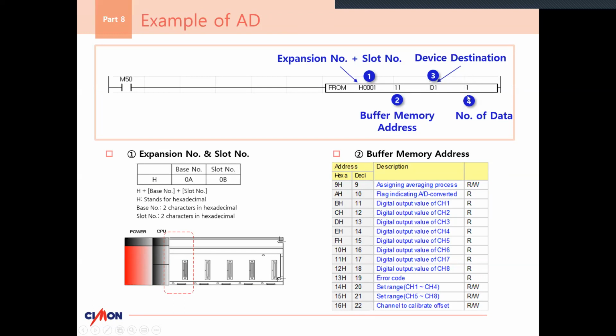If we had a 2 right here, we would want to make sure that we don't touch D2 with anything else, because it's going to send 1 word to D1, and then it's going to send another word to D2 consecutively, depending on what number we put here for number 4. So just to recap, it's going to take buffer memory 11, so channel 1, from expansion 0, slot 1, and it will in turn put that data into the CPU at location D1 in a total of 1 word of data.